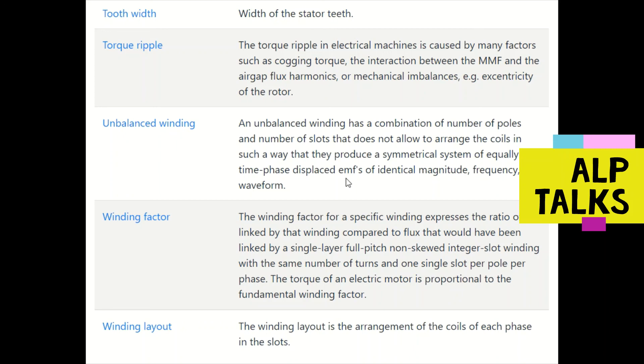Winding factor for a specific winding expresses the ratio of flux linked by the winding compared to what would have been linked by a single-layer, full-pitch, non-skewed integer slot winding with the same number of turns and one slot per pole per phase. The torque of an electric motor is proportional to the fundamental winding factor. Winding layout is the arrangement of coils of each phase in the slots.